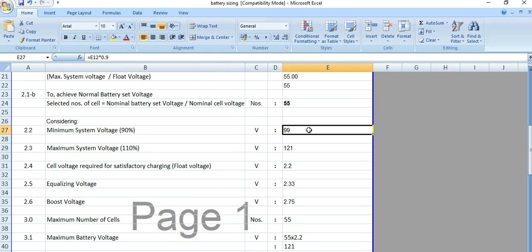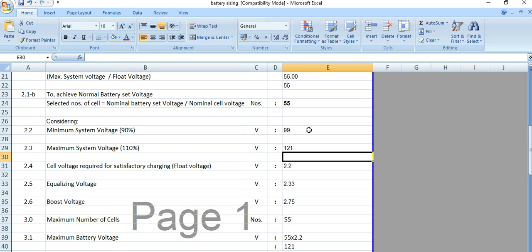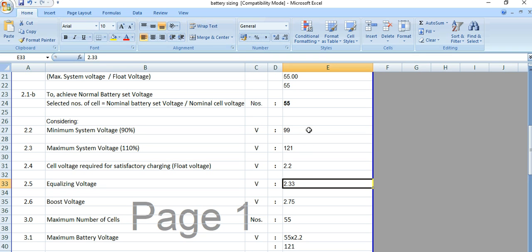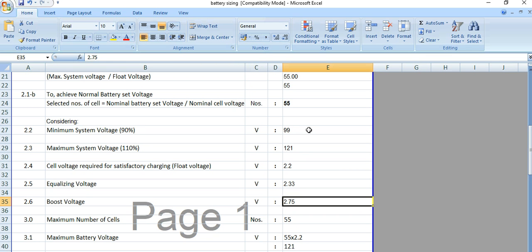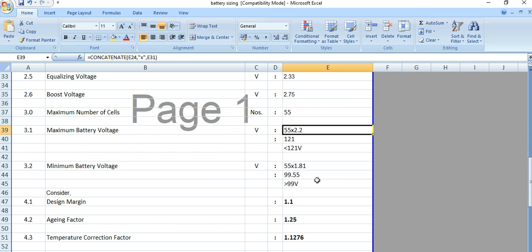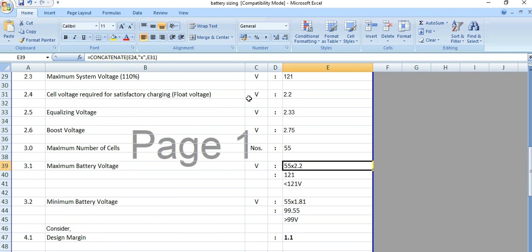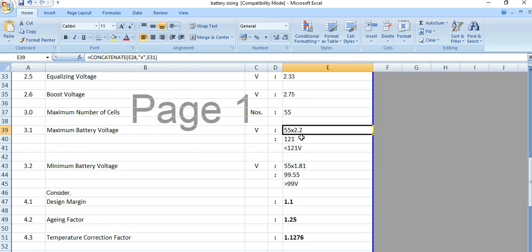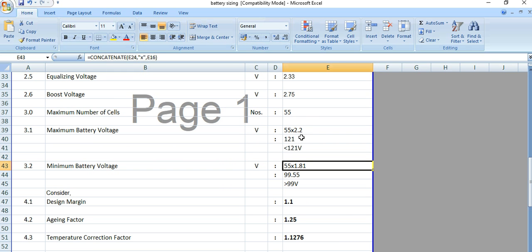We have considered minimum system voltage as 90%, maximum system voltage as 110%, and float voltage as 2.2 volts. Equalizing voltage is 2.33 volts and boost voltage is 2.75 volts — these come from the battery manufacturer. Maximum number of cells is 55, so maximum battery voltage is 55 multiplied by 2.2, giving 121 volts.